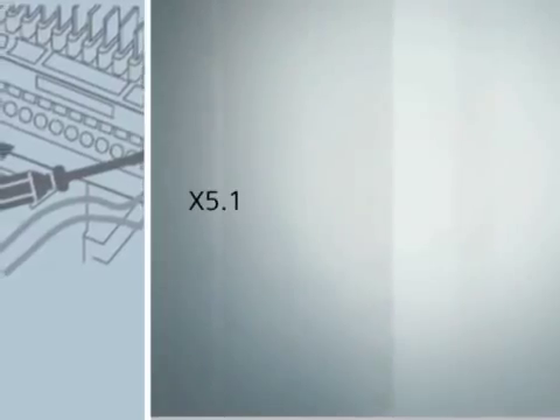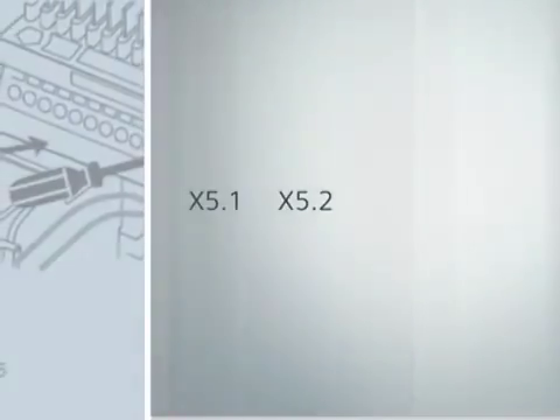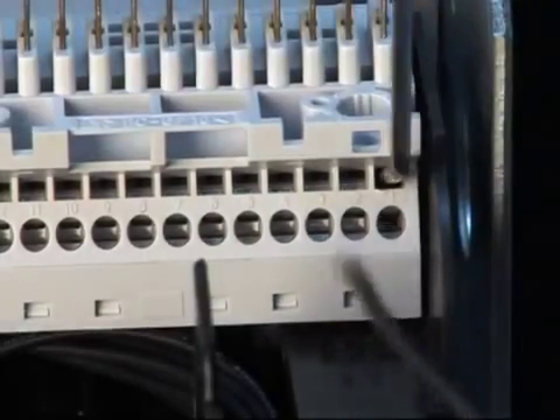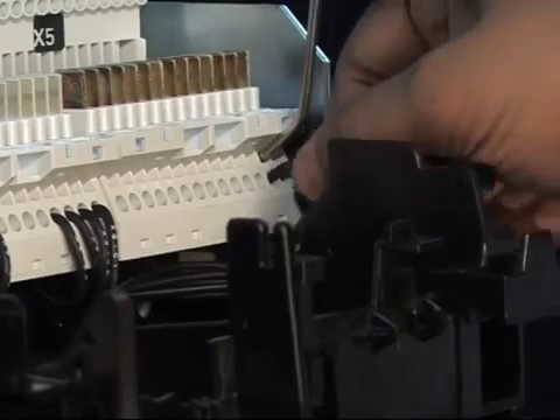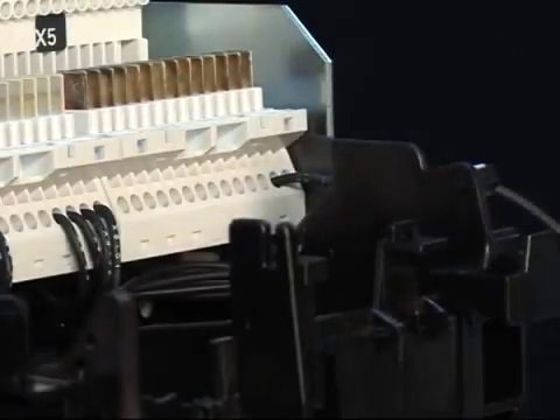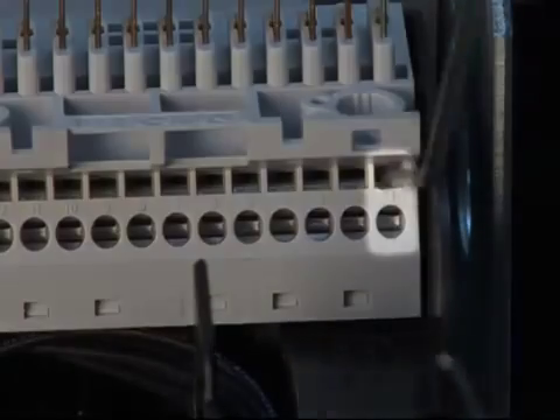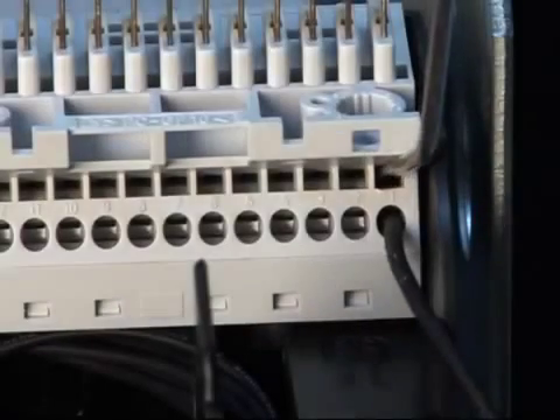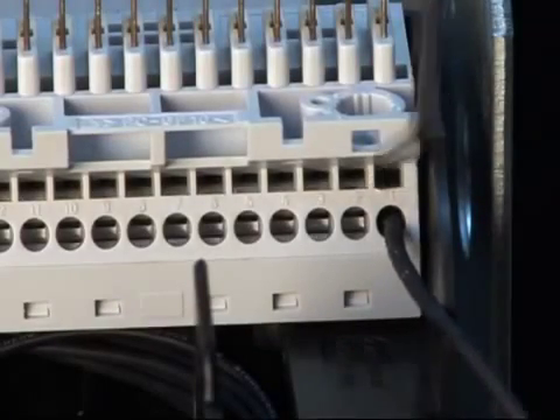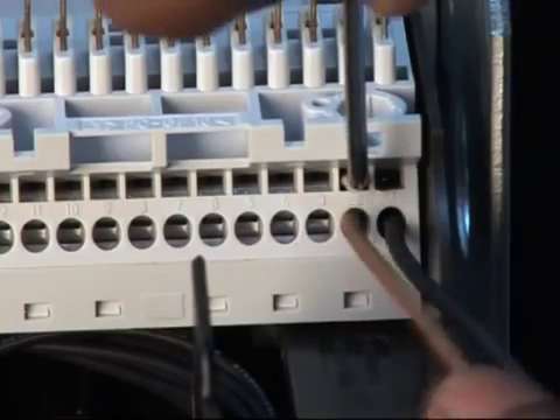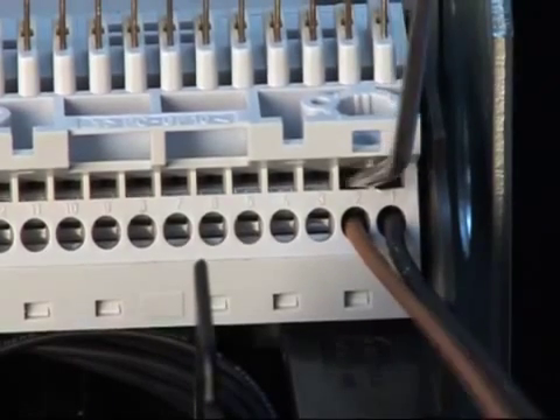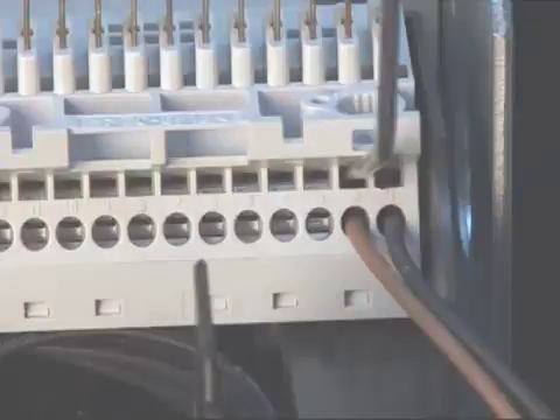The wires are terminated at X5.1 and X5.2. The unique Sigut termination does not require any screw fixing. Just press with a screwdriver in the slot above the auxiliary wire terminal to open the spring-loaded terminal. Remove the screwdriver once the wire is inserted and it will be held tightly. This reduces the complexity and wiring time greatly.